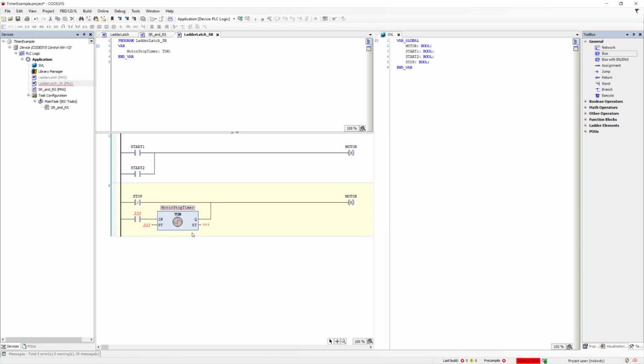As we can see, we can use a function block within the ladder diagram. In order to do that, the function block needs to send out at least one signal that is a Boolean, because the ladder program uses Booleans, but we can still have this signal that is a time, but they are not connected to the ladder rung here. I remove the question marks for ET. I set the time, T hashtag. I will use 10 seconds this time, and the variable motor that will start the timer. I've done the same thing but in ladder.